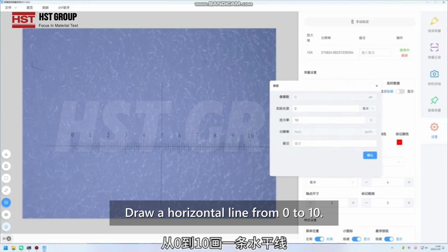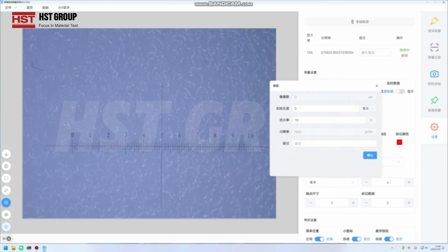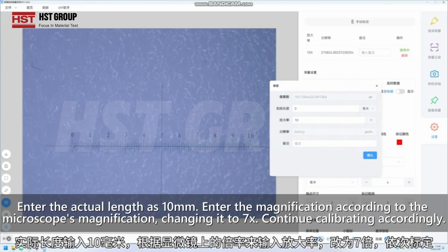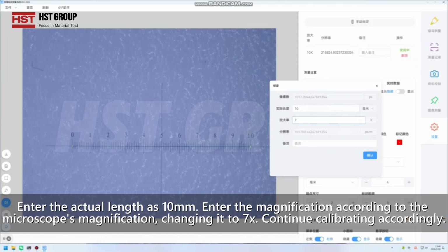Draw a horizontal line from 0 to 10. Enter the actual length as 10 mm. Enter the magnification according to the microscope's magnification, changing it to 7x. Continue calibrating accordingly.